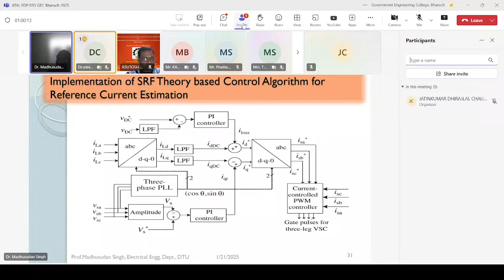This loss, usually we understand as the losses in the switching devices, and also, if the battery bank is there, the internal resistance loss. To cover those losses, this VSI needs to draw some real power from the source. So this is how it maintains the DC link. I hope this is clear. The two components of current, one responsible for real power transfer and the other for reactive power transfer, need to be clearly distinguished. Finally, these two-phase currents again need to be transformed to the corresponding three-phase reference current. This three-phase reference and the actual three-phase source current are then compared to operate a hysteresis current controller. So here is a three-phase hysteresis current controller, which will finally generate 6 PWM signals for that VSC.